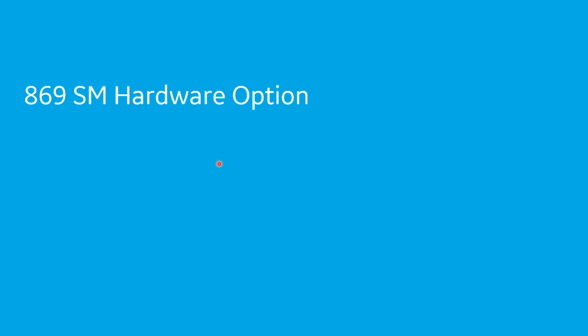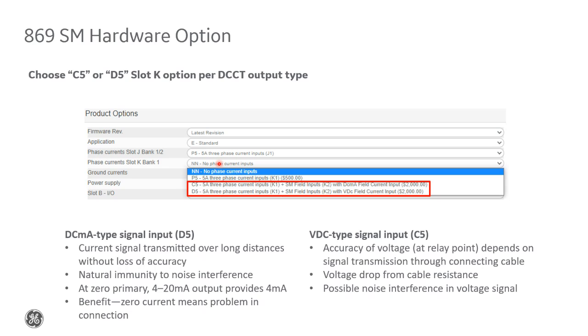So we've covered some of the key elements specific to protection and control of a synchronous motor provided with the 869 synchronous motor option. Now just a few points on the hardware aspect of it. To select this option to start with, there's one code in the model number that you need to specify. In the second phase current option, slot K, you can either choose P5, which gives you a second set of CT inputs that can be used for differential CTs.